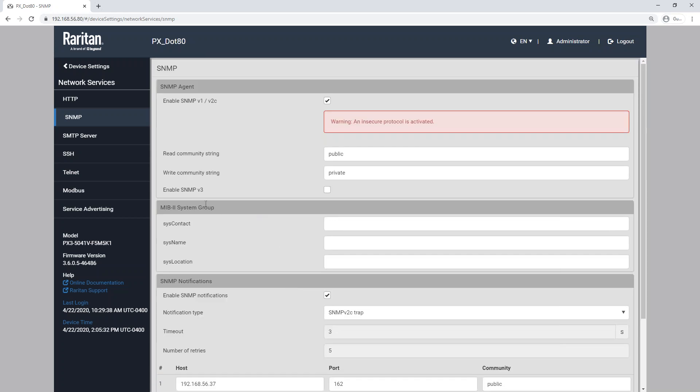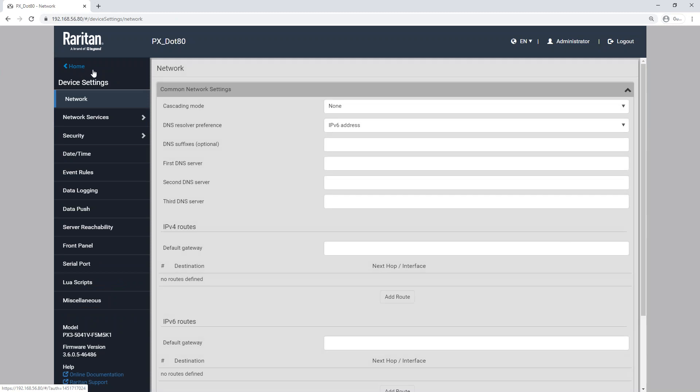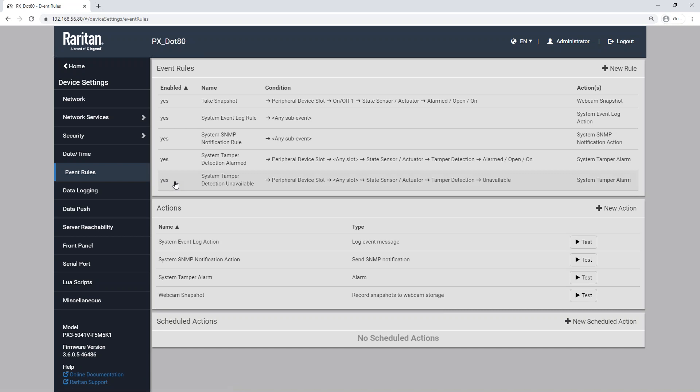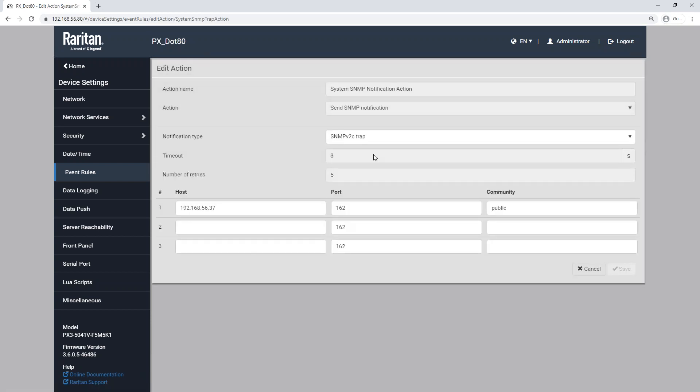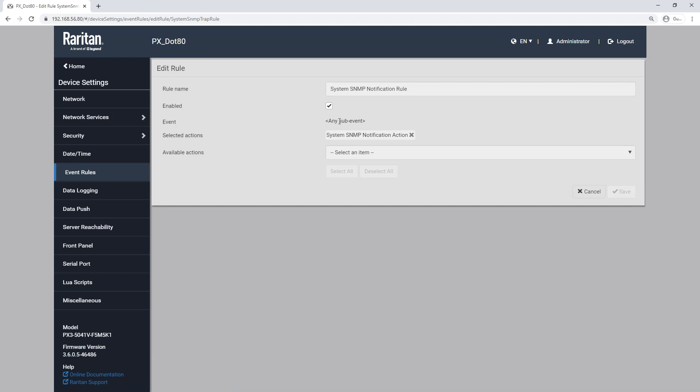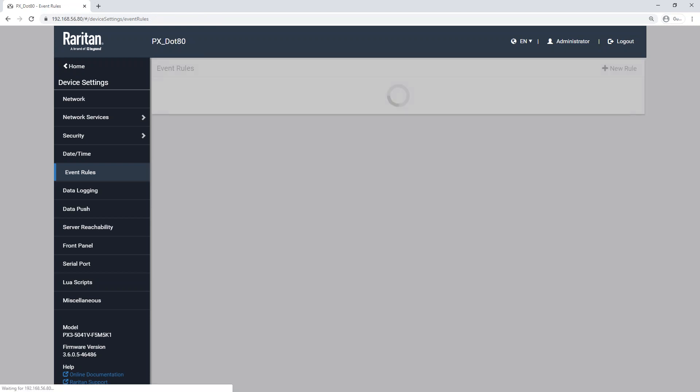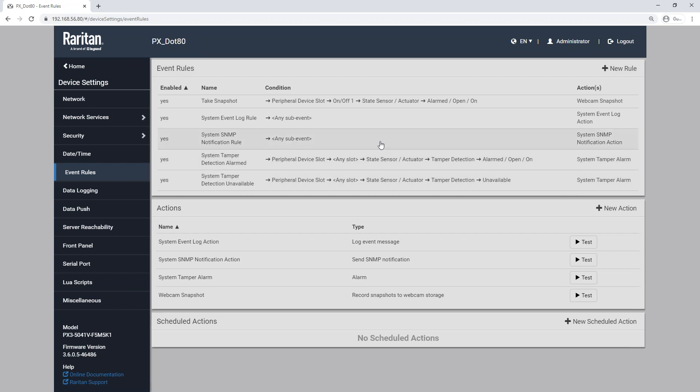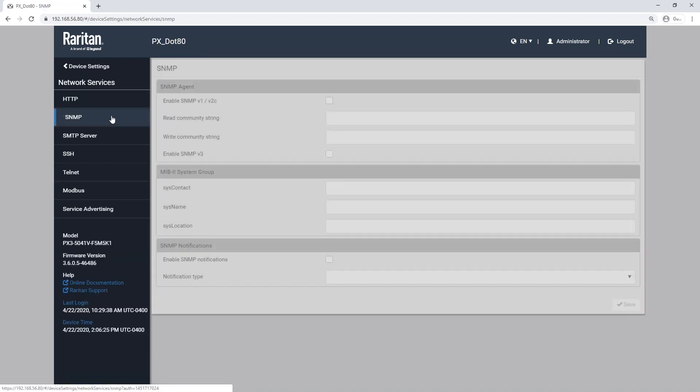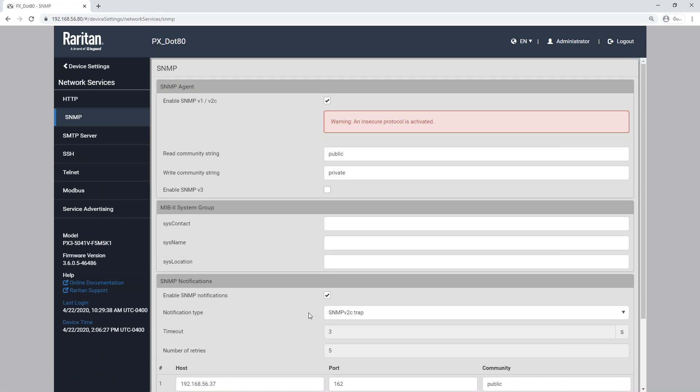Now those changes are saved. Now, one thing that I want to show you is if we go back into the device settings menu, we have event rules. So after we set up that SNMP notification in the SNMP menu, what is configured here is an action that basically the same menu that we just saw, but it is set up as an action. And then we have an event rule that triggers that action. This event rule is anything that happens on the PDU. So it's a catch all. So any sub event on the PDU will get sent to our SNMP manager so that we have a nice log of everything that's occurred. So I'm not going to modify that because that's set up exactly how we need it to be. So that is SNMP. So really all you have to do is add in that SNMP manager information and enable notifications.